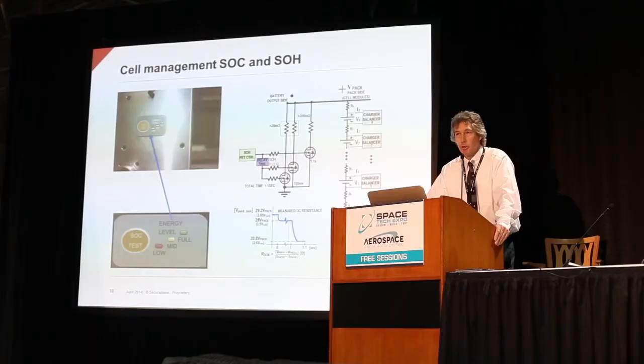However, within the Securaplane batteries that exist today, we offer a state of health that has internal current draw elements that do a multi-stage discharge on the battery at particular times, allowing the data to be put into an algorithm that involves temperature, number of discharges, and other parameters that can give a much better indication on the spot of state of health than is typically provided.